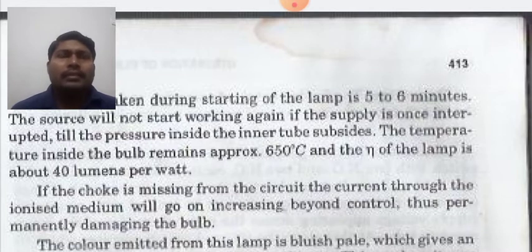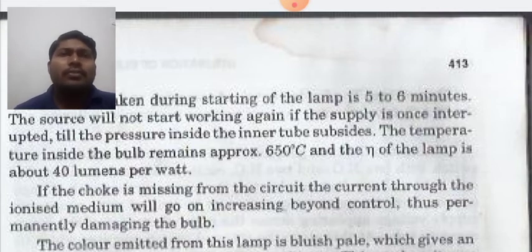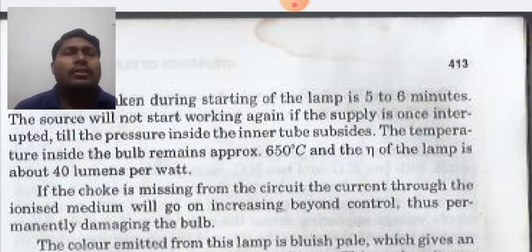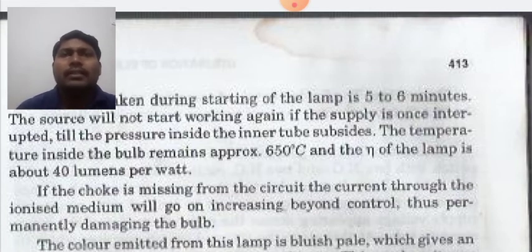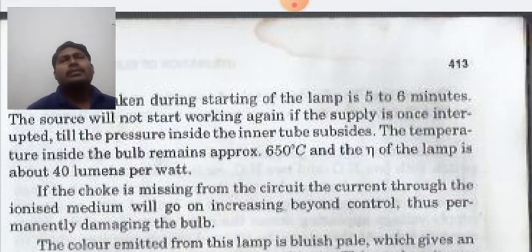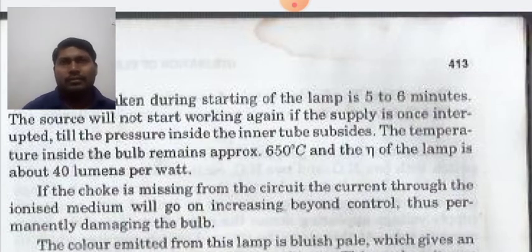The lamp will not start working again if the supply is once interrupted until the pressure inside the inner tube subsides. The temperature inside the bulb remains approximately 650 degrees centigrade. The efficiency of the lamp is about 40 lumens per watt. If the choke is missing, the current through the ionized medium will go on increasing beyond control, permanently damaging the bulb. You should never use it without a choke.